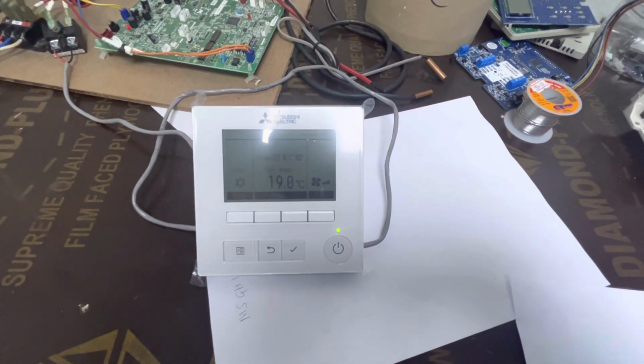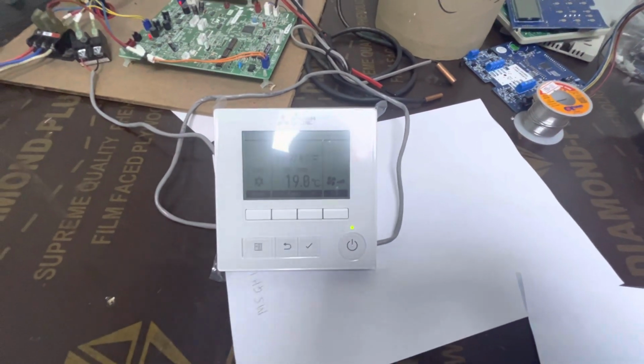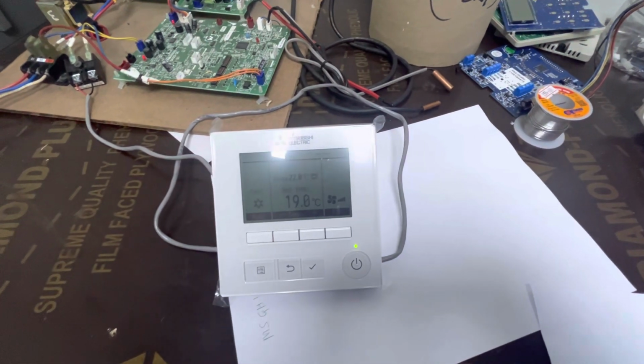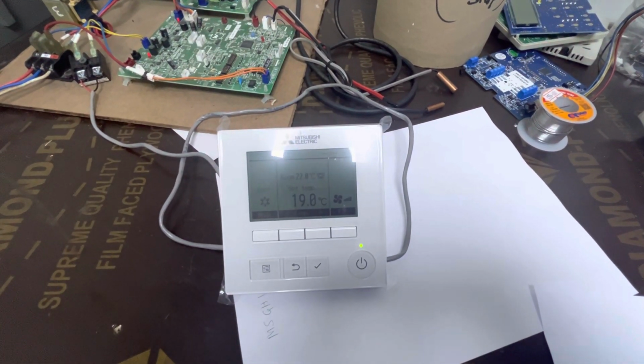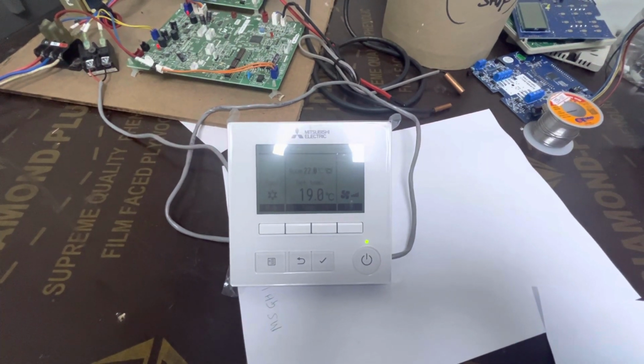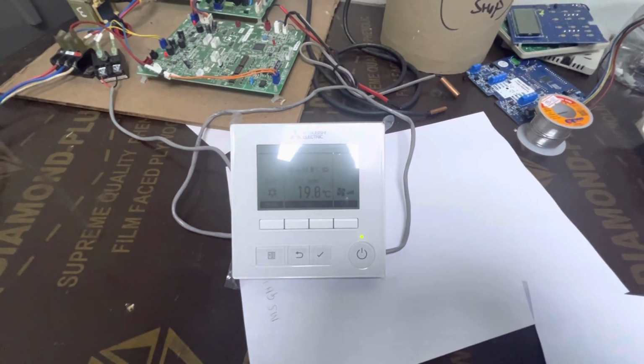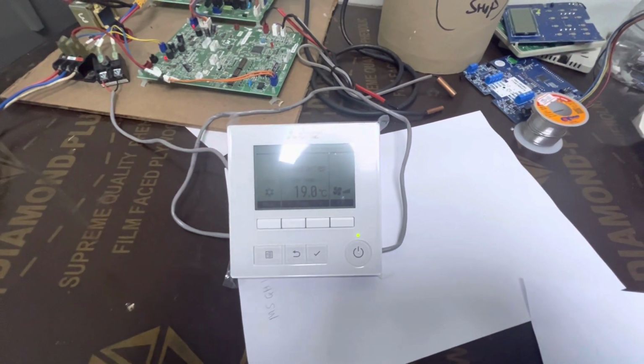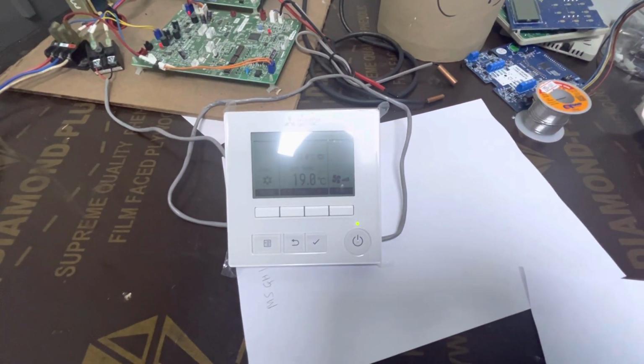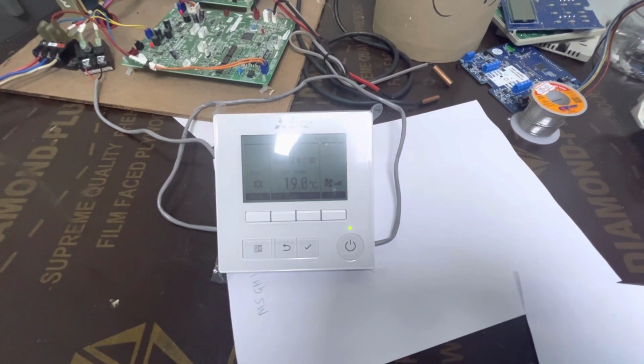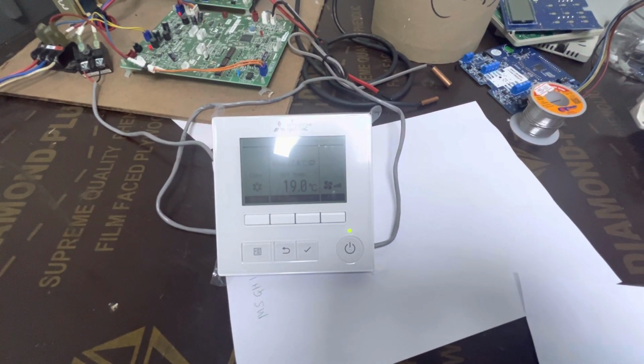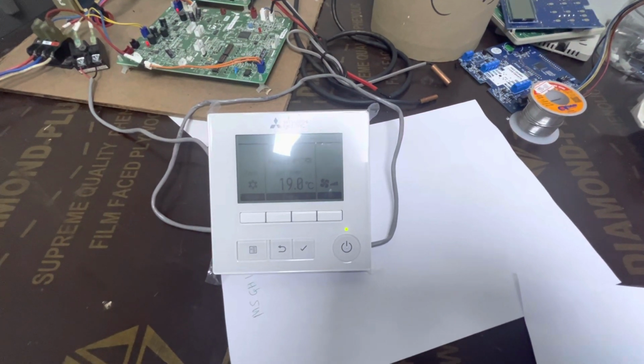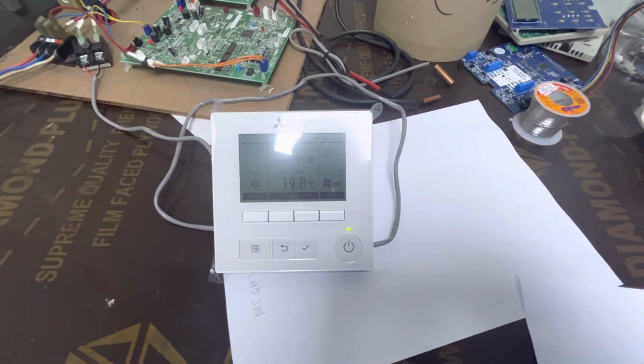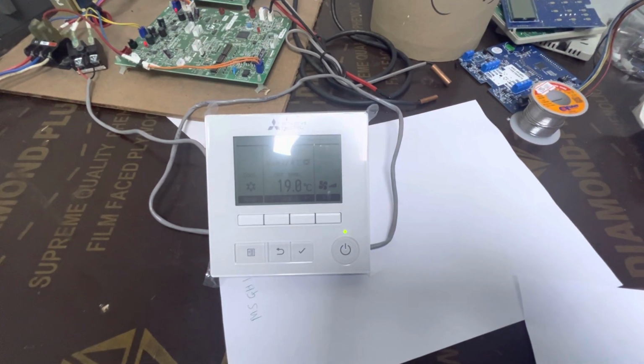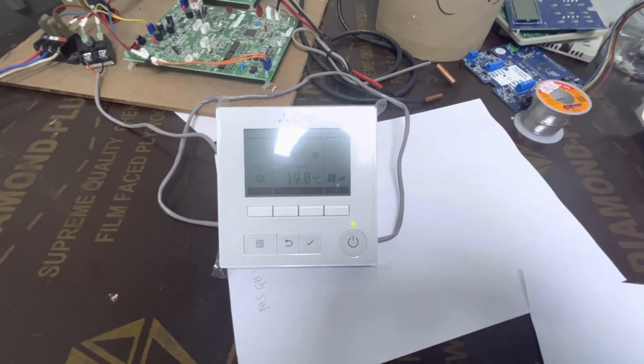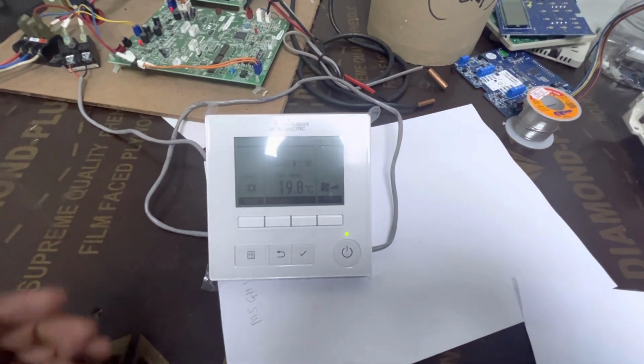So there is a Pascal setting, like 50 Pascal, 100, 150. Whatever Pascal is required during commissioning, you need to check with a barometer or anemometer. Check the airflow, check all the grills and diffusers, and how much airflow is required for each point. So you need to adjust that during commissioning. That static pressure you can set from the thermostat for the Mr. Slim model, and I will tell you how to make that setting.